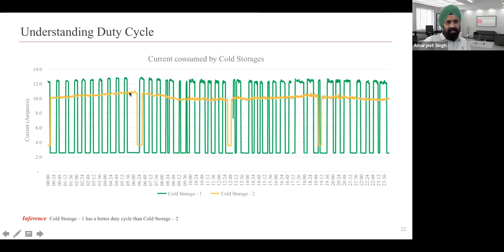So what we do is we look at the duty cycling, right? This duty cycling should not be very low, because very low duty cycling either means that you have put in a very low set temperature, which the compressor cannot achieve, and therefore the compressor is always on, or perhaps the compressor has some fault, like maybe there is a gas leakage, etc. And therefore the compressor is not able to cope even with the nominal set point, right? So very low duty cycle is bad.